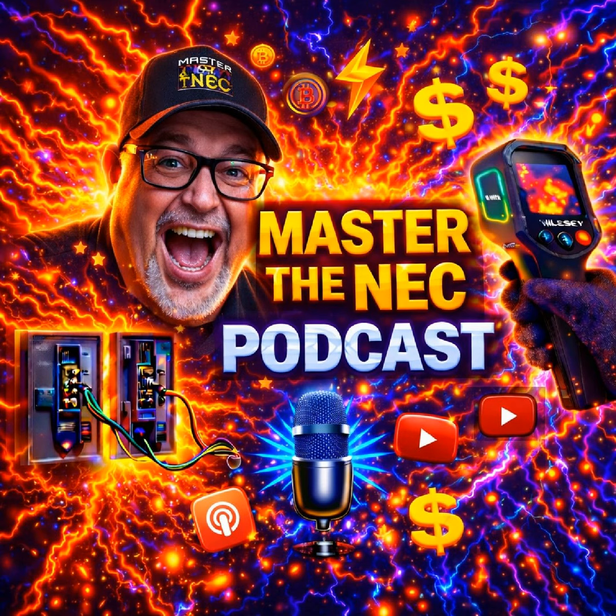So if current leaves the source through a person and travels into the earth, I want you to ask me something. Paul, how does it get from the earth back to the source winding? That's an incredibly important question. And that brings us to floating generators or unbonded generators. So you have to always ask yourself, Paul, it could flow through me and it could go through me to the earth, but doesn't it have to get back to the source? How does that happen? And so let's talk a little bit about a floating generator and unbonded generator.